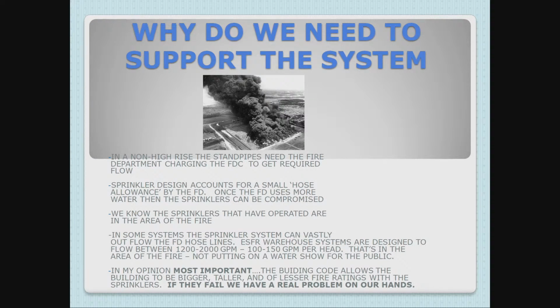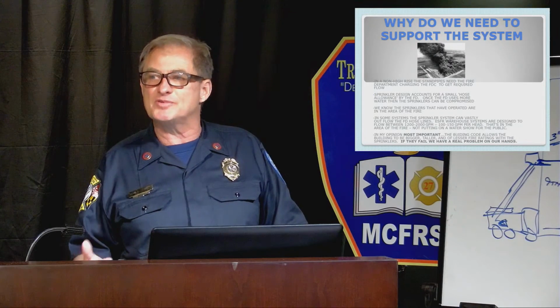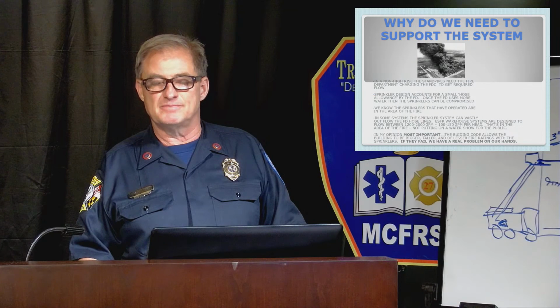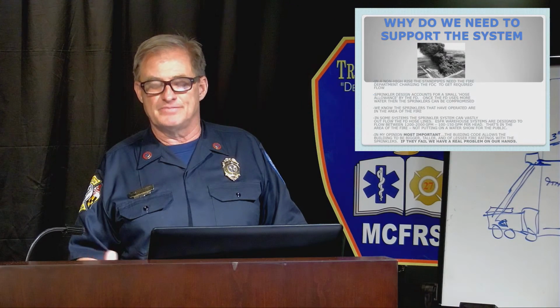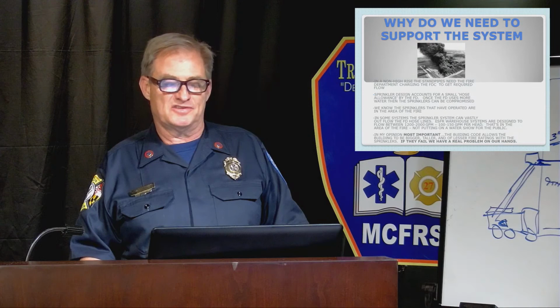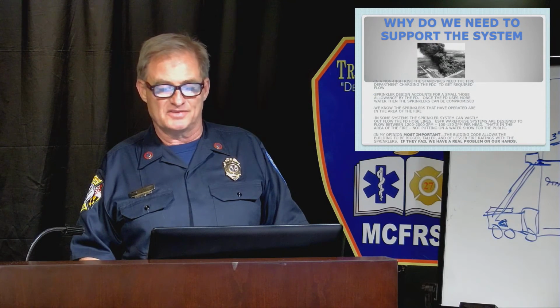Another thing, which accounts for that grocery store that burned down, accounts for that Fairfax building that burned, is the sprinkler design accounts for the fire department to use a certain amount of water and then support the system. So if the fire department rolls in and starts flowing more water than the design has accounted for, it pretty quickly robs water from the sprinkler system. And that's important. So supporting the system, it's not an option, it's a must.